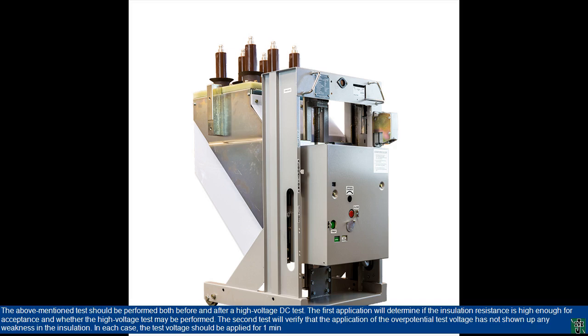The first application will determine if the insulation resistance is high enough for acceptance and whether the high-voltage test may be performed. The second test will verify that the application of the overpotential test voltage has not shown up any weakness in the insulation. In each case, the test voltage should be applied for 1 minute.